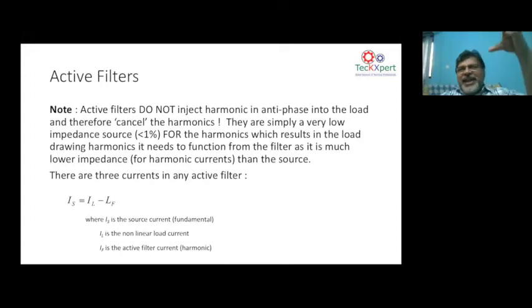Now, if you put a transformer with the rest of the network, the source impedance of the network is much higher. You put an active filter in parallel, which has a much lower source impedance, so the load will always try to go to the active filter, which is a low source impedance, and take the harmonic currents from there instead of taking the harmonics from the network. So that means the active filter produces harmonics as a low source impedance device.